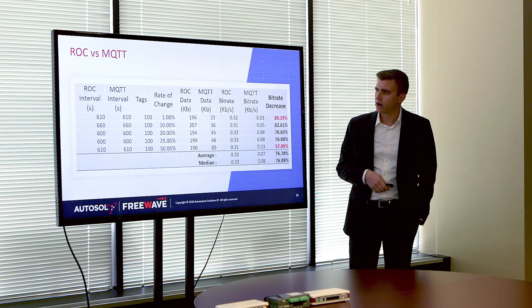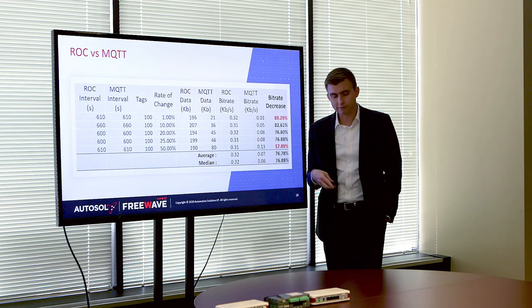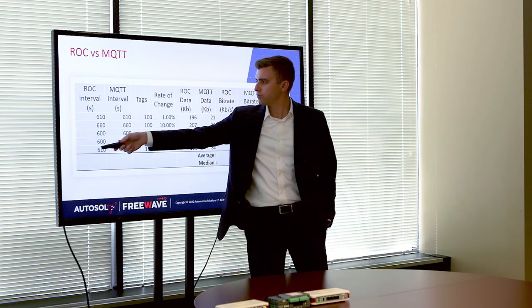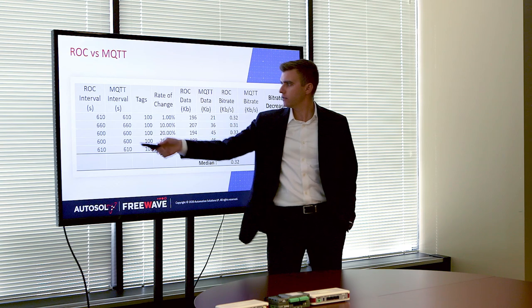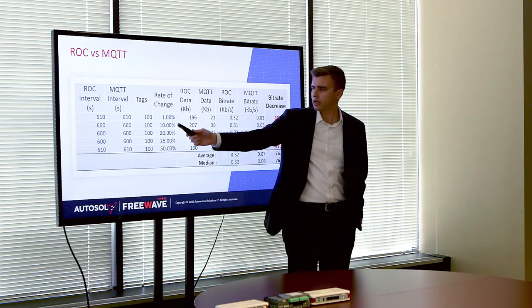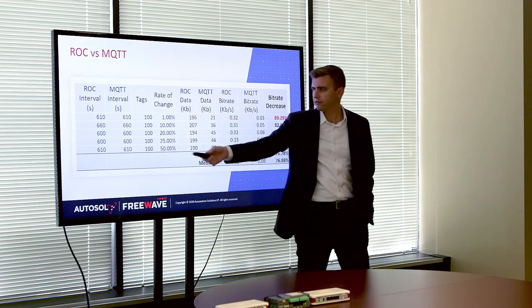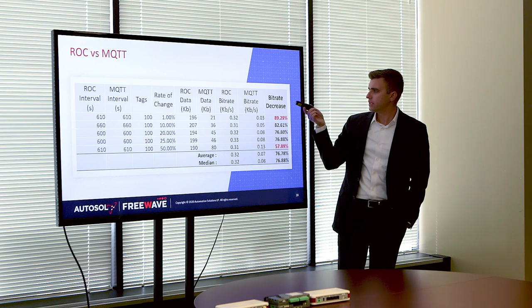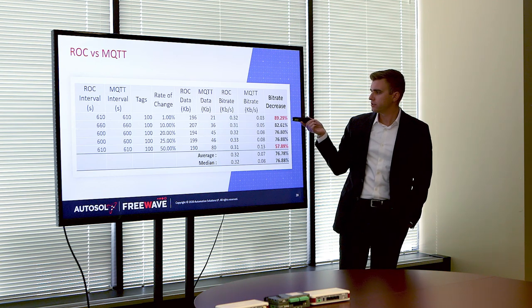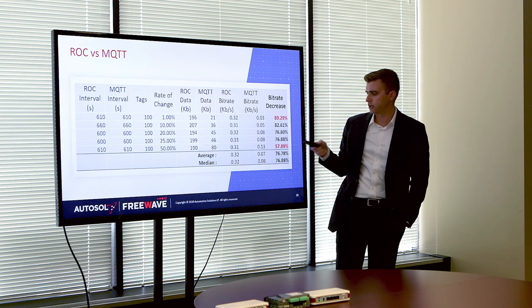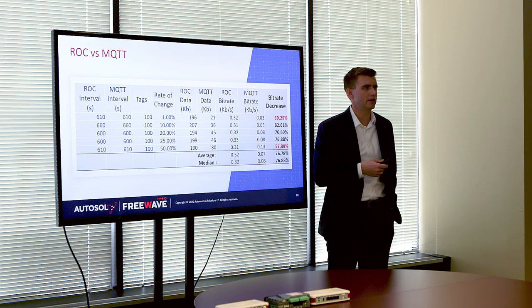For ROC it's the same story as Modbus — 10-minute polling, 100 tags, rate of change 1%, 10, 20, 25, and 50. The bit rate decrease between 1% change was 89% reduction and 50% was 57.89% reduction. Not as shocking as Modbus results, but still very effective in the field.